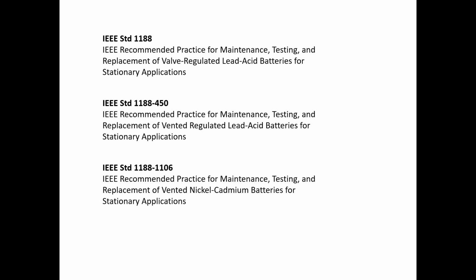The standards that most people work under are the IEEE. Utilities also have some other standards, North American Electric Reliability Council, the NERC, and there's a federal NERC and FERC, as it's referred to, comes into power generation. But for most telecommunication, UPS, and switchgear utility and chemical, petrochemical applications, IEEE is the standard by which most people write their routines around. Their maintenance is usually written around their specifications or their recommendations.